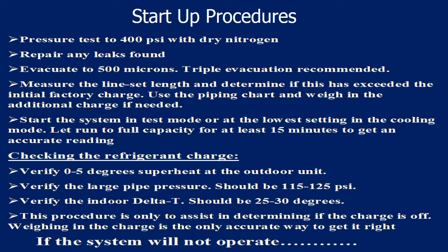Make sure both service valves are completely opened and back-seated. Select the cooling mode, which is indicated by the snowflake on the remote controller, and set the set point down to its lowest setting. There is a standard 3-minute delay before the outdoor unit will start. Allow the system to operate for a minimum of 15 minutes before referencing any pressures or temperatures. These systems operate at a 0 to 5 degree superheat and a 20 to 25 degree delta T across the indoor coil when properly charged.